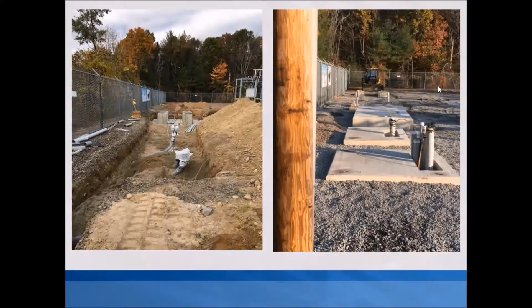The first conduit group is where the main transformer feeds between the pole or recloser. The next group is where the auxiliary transformer is. We did the auxiliary project to be sure we could monitor round trip efficiency, which is very important, as well as the parasitic load that any project like this can place on your system. So we track it separately, each one individually metered so we can track it better.